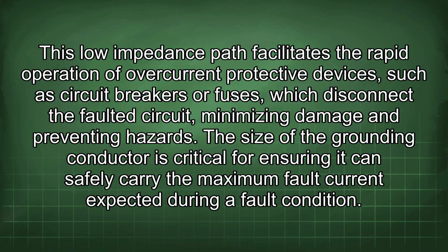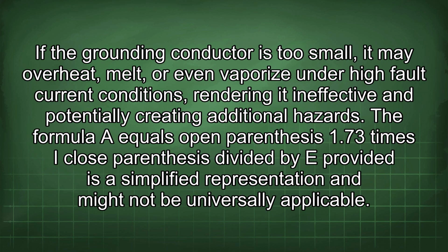The size of the grounding conductor is critical for ensuring it can safely carry the maximum fault current expected during a fault condition. If the grounding conductor is too small, it may overheat, melt, or even vaporize under high fault current conditions, rendering it ineffective and potentially creating additional hazards.